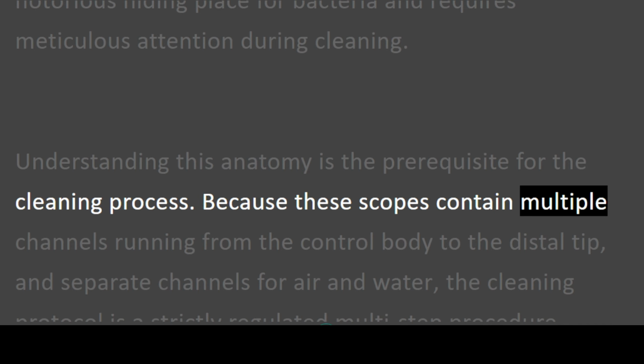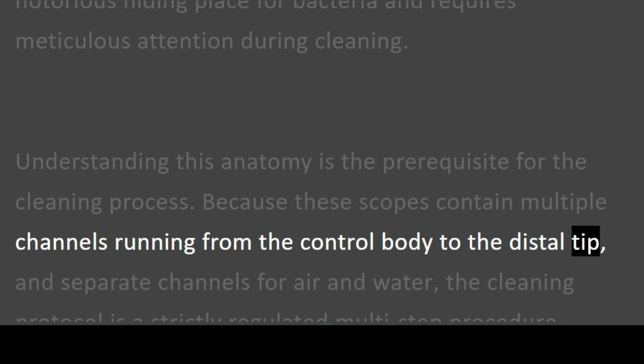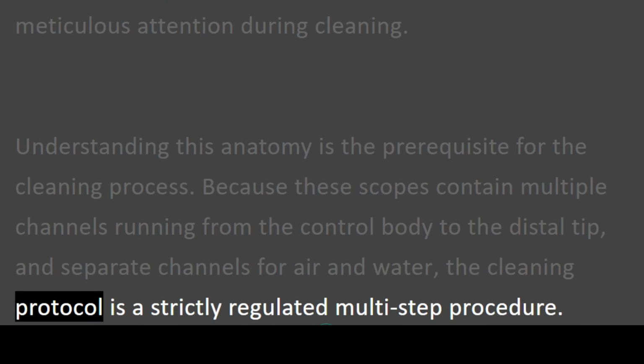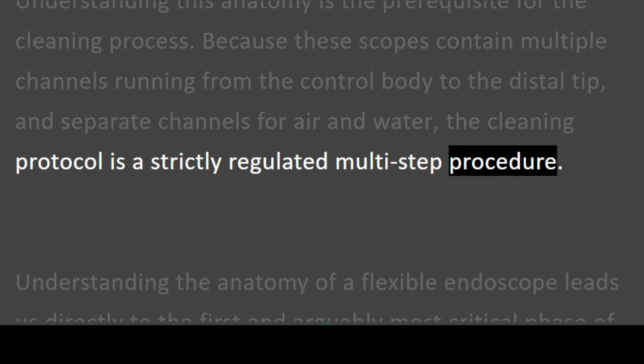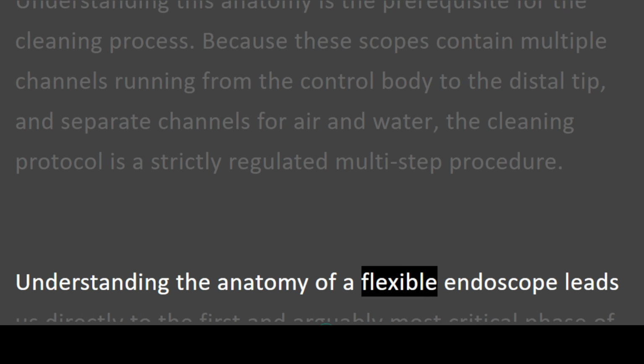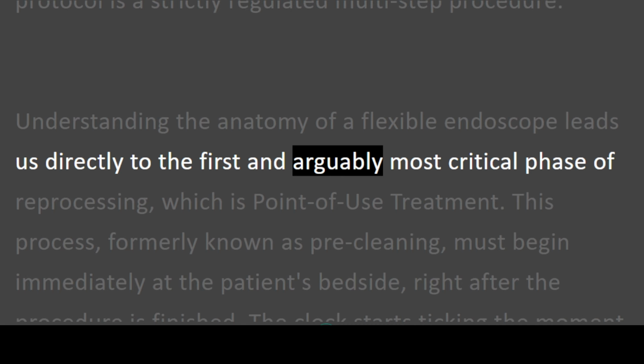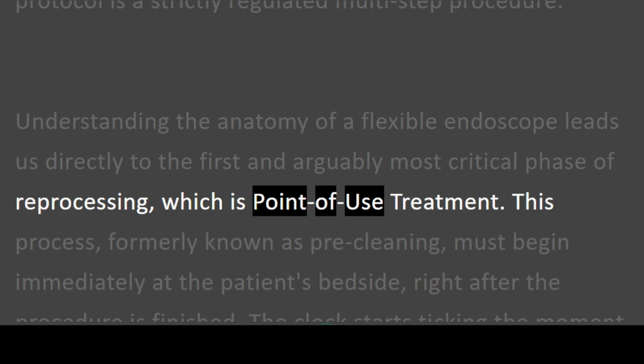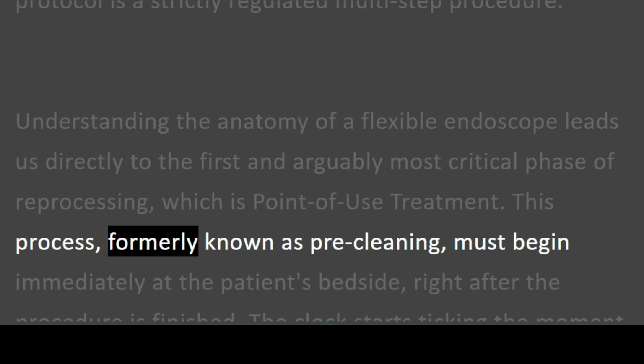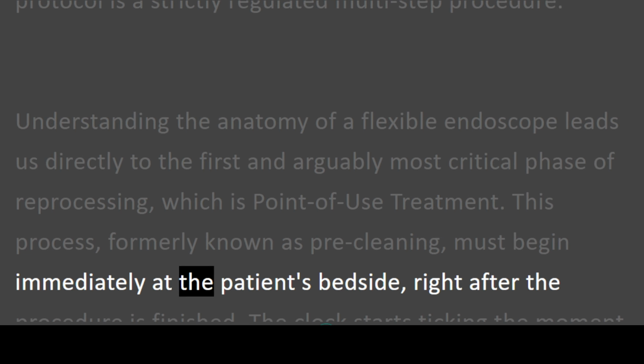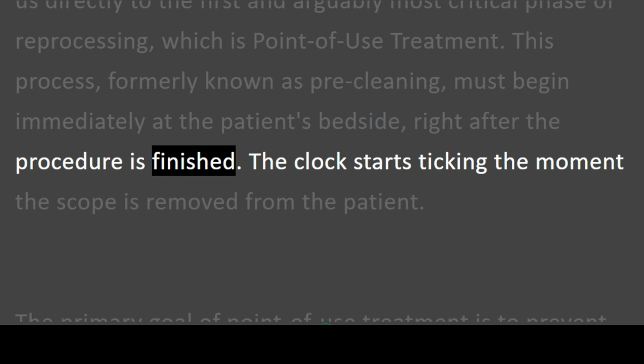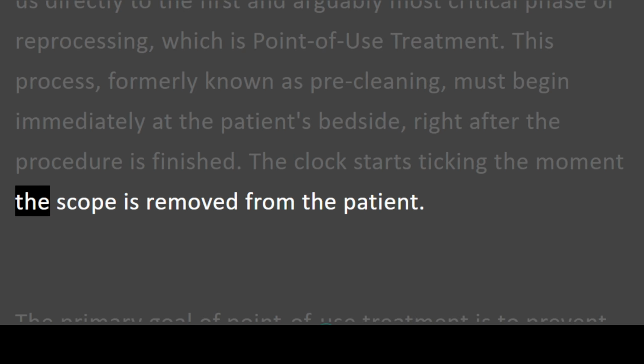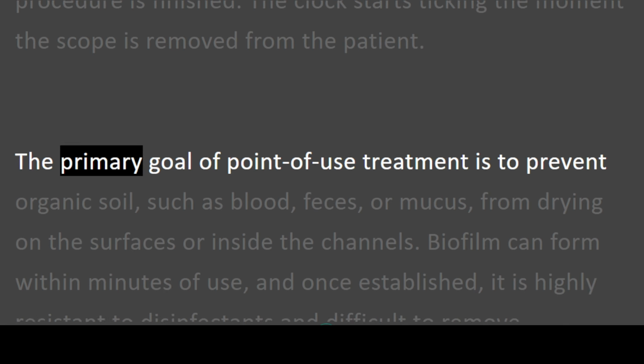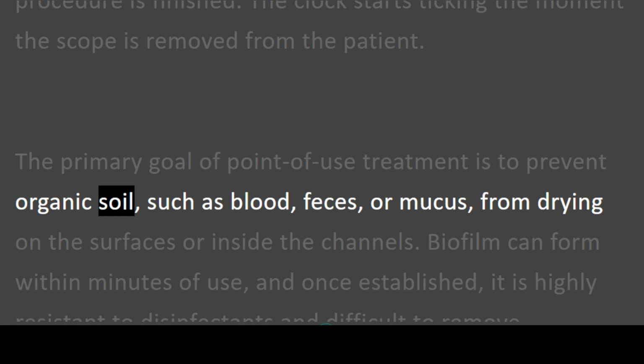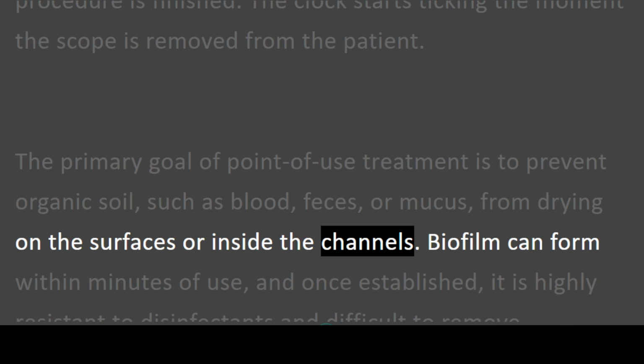Because these scopes contain multiple channels running from the control body to the distal tip, and separate channels for air and water, the cleaning protocol is a strictly regulated multi-step procedure. Understanding the anatomy of a flexible endoscope leads us directly to the first and arguably most critical phase of reprocessing, which is point-of-use treatment. This process, formerly known as pre-cleaning, must begin immediately at the patient's bedside, right after the procedure is finished. The clock starts ticking the moment the scope is removed from the patient. The primary goal of point-of-use treatment is to prevent organic soil, such as blood, feces, or mucus, from drying on the surfaces or inside the channels.